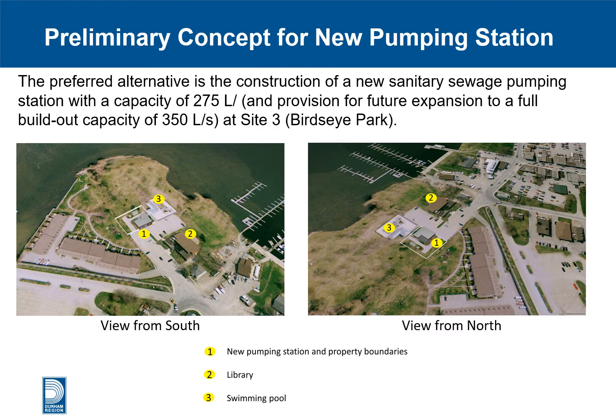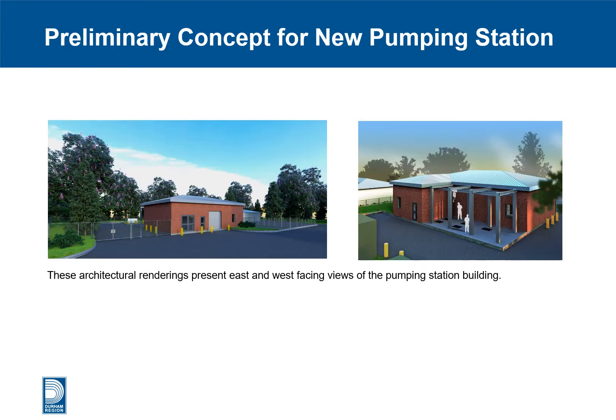The preferred alternative located in Birdseye Park will involve construction of a new pumping station with a capacity of 275 litres per second during phase 1, with provision for future expansion to a full build-out capacity of 350 litres per second. As shown in the slide graphics, the pumping station will be located adjacent to the swimming pool on the west side and across from the library to the north. Once constructed and commissioned, the existing Water Street Sanitary Sewage Pumping Station will be decommissioned and demolished. Architectural renderings of the east and west facing views are provided to represent a typical sanitary sewage station, though the detailed design process has not started and the look of the facility is subject to change.